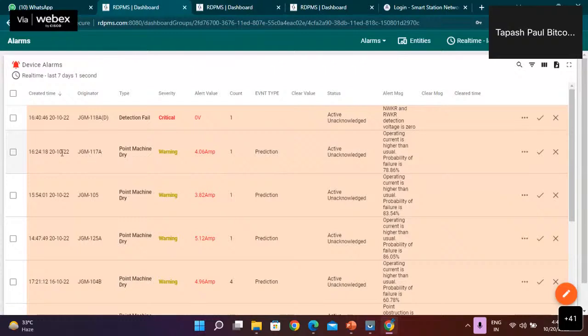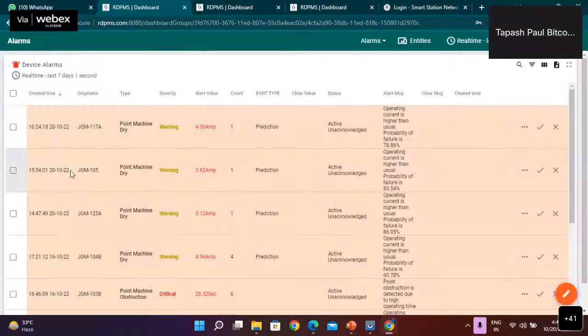So I can see here on this date, 20-10-22 at 15:54 hours, JGM 105 point machine is drying and the severity is warning. Alert value is 3.82, and this is a prediction type alarm showing that operating current is higher than usual, with the probability of failure of this point machine at 83%.